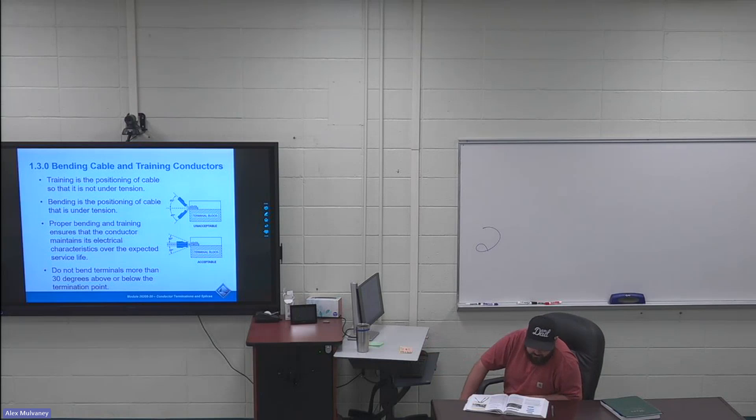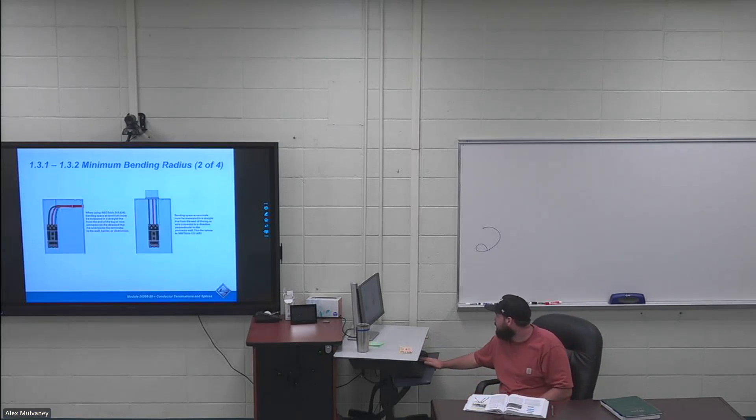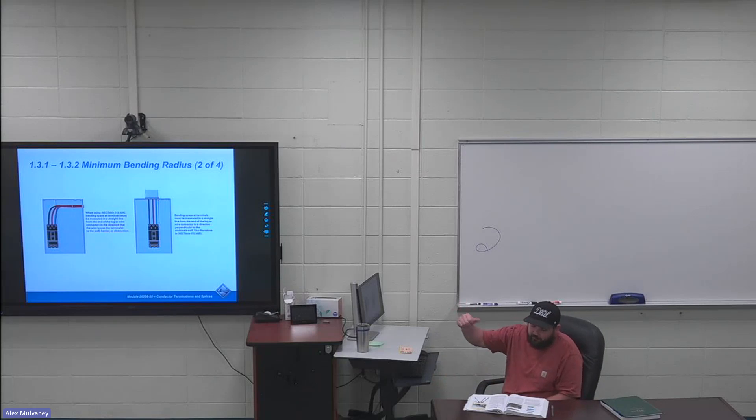First sentence in Section 1.3.0 on page 6 is highlighted. Training is the positioning of cables so that it is not under tension. So that's making sure that you're not, like you can see the picture on the board. Training wire. Looking at the picture on page seven in the top right, I would never want my wires pulled tight around the corner of that conduit. So I would bring them up and bend them so that there's no tension on the conduit or coming right inside the box, anything like that.